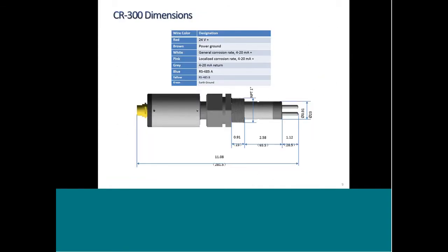And also, how do you want those installed? Are they installed in a flow assembly? Because you're 1-inch MPT, and I think standard is 3/4. So that was a challenging decision based on the opportunity of where we thought the majority of these units would be sold, as to whether to design them in 3/4 or 1-inch. And the vast majority of requests was 1-inch, so that's what the design came to. That may represent a little bit of a modification need in the mid-market, because I do know that 3/4-inch tends to be more common.